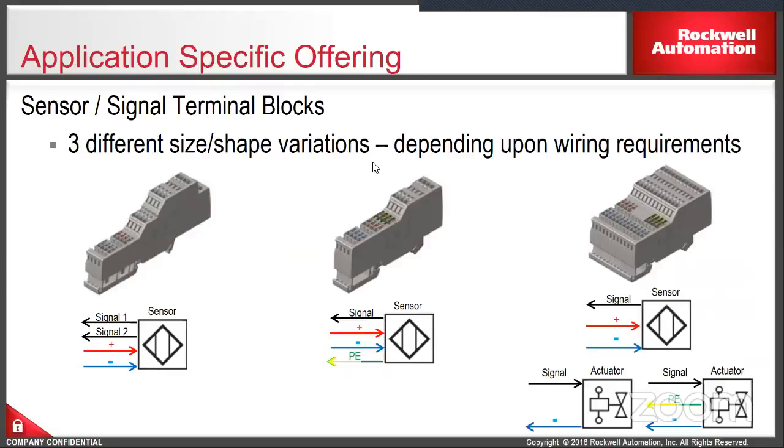So, benefits: once again, it is UL tested, and basically they take 2 wires, stick them in, and pull them apart. The terminal block will actually break before the wires come out of the socket. I don't know if you are using ferrules, but it's highly recommended to use ferrules for these. Some of the larger shops use ferrules; they have the machine you stick the wire in to get a ferrule out. But if not, you can use straight wire as well, with a screwdriver.